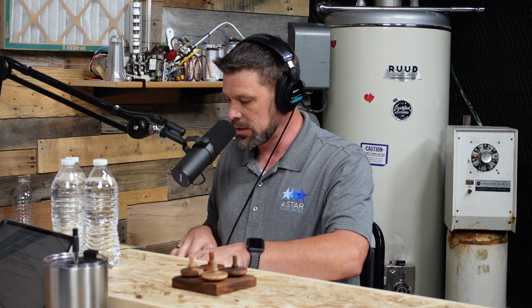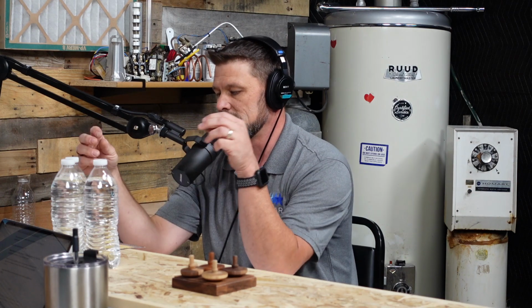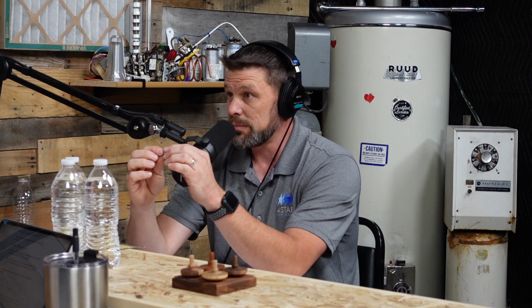But if we dive into what a reverse osmosis membrane does, the membrane size is 0.0001 microns, so it's just way, way, way tiny. The membrane is almost like a paper with little teeny holes in it. Yep. As the water passes by, the water molecules can pass through. Everything above that 0.0001 gets trapped, and then another flushing system flushes it down the drain. Gotcha. Most bacteria are going to be 0.2 microns in size, so they're way too big to fit through that semi-permeable membrane.